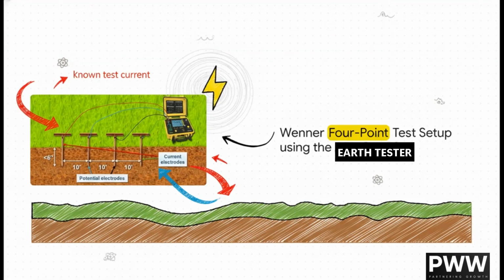Moving on to Section 2, Soil Resistivity Testing Methods. Now, what's really interesting about the pre-design phase is that before we even think about engineering a ground grid, we have to measure the earth itself. The Wenner 4-point setup is universally recognized as the absolute most accurate technique for this job. You drive 4 equally spaced probes into the ground in a straight line. Then, an instrument injects a known test current through the 2 outer stakes and measures the resulting voltage drop across the 2 inner stakes. It's a really elegant, highly effective way to scan the different layers of the earth.